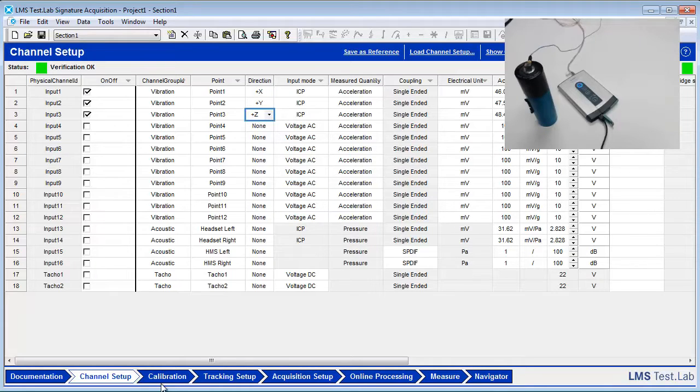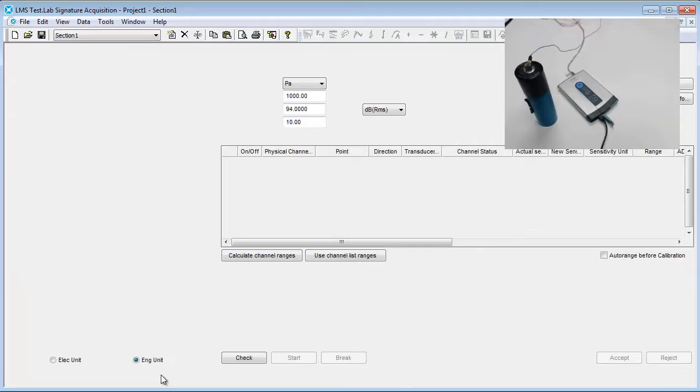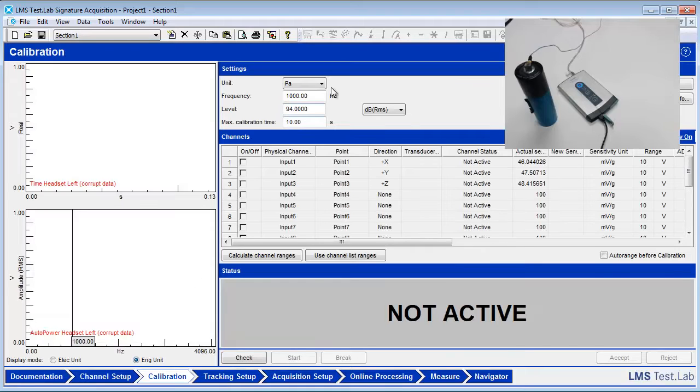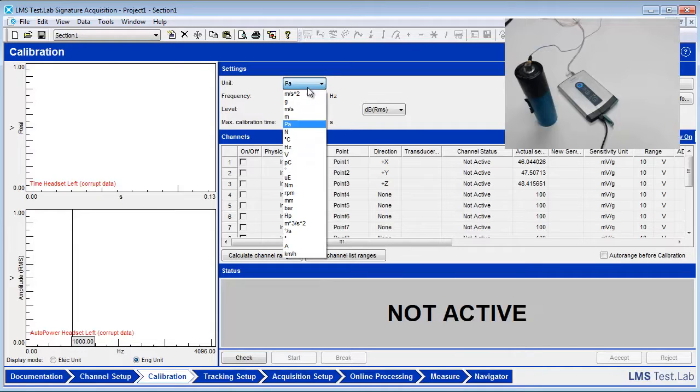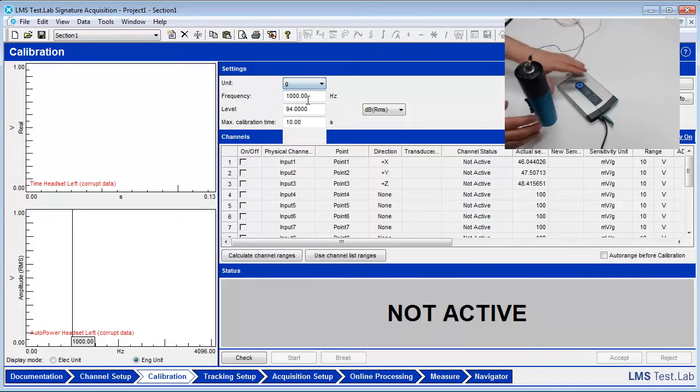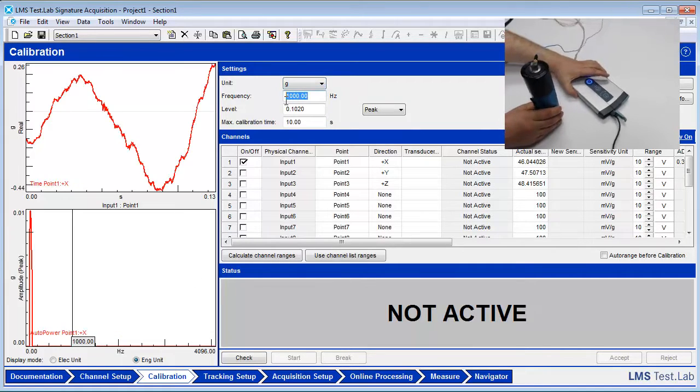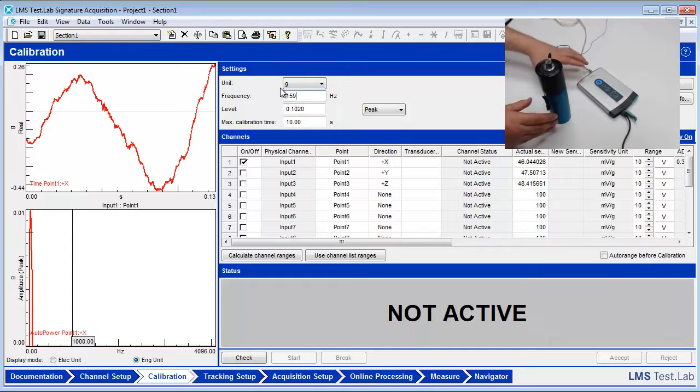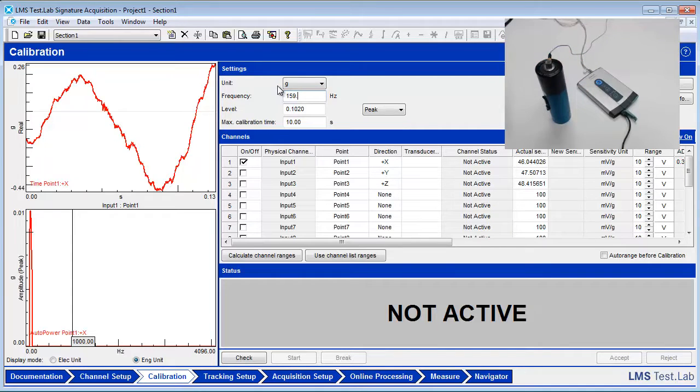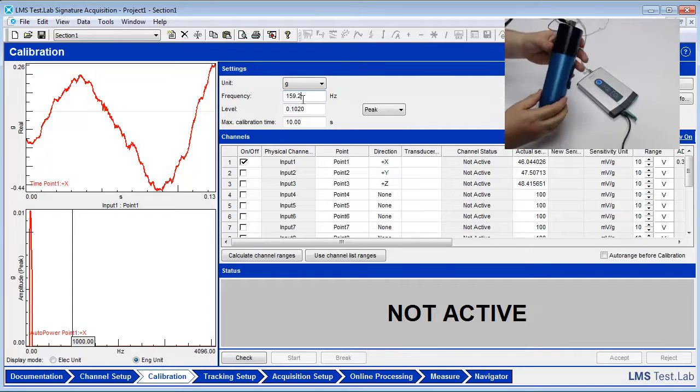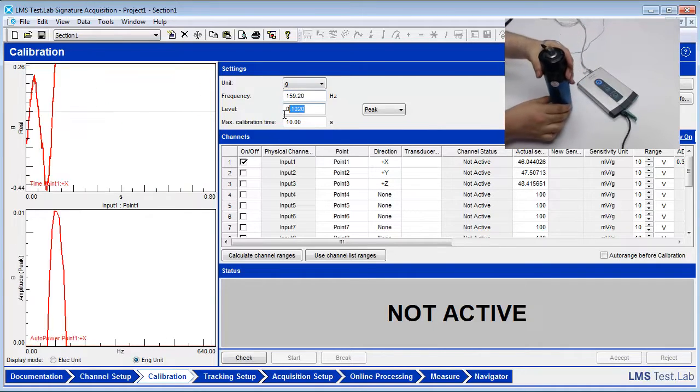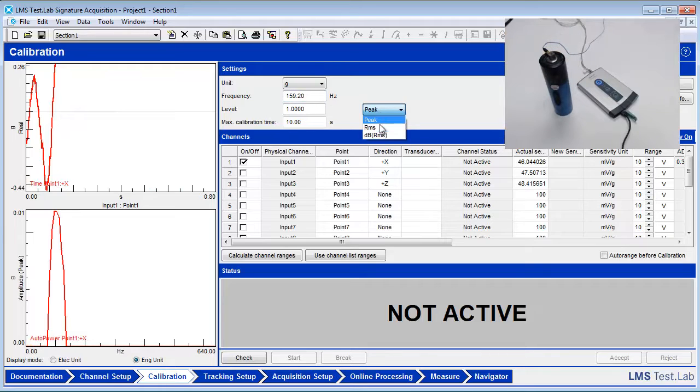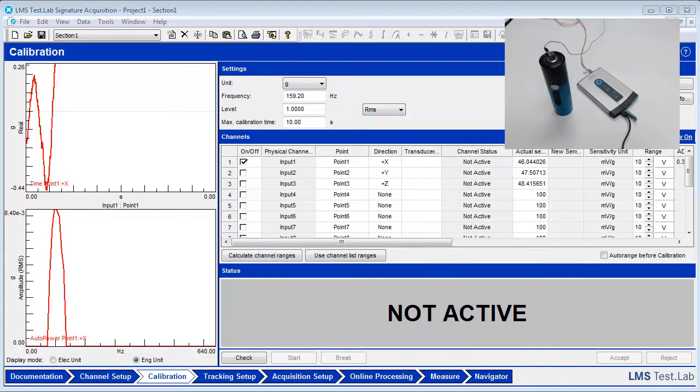In the calibration worksheet, change the unit to G, the frequency to 159.2, and the level to 1 RMS. These settings are specific to the calibrator.